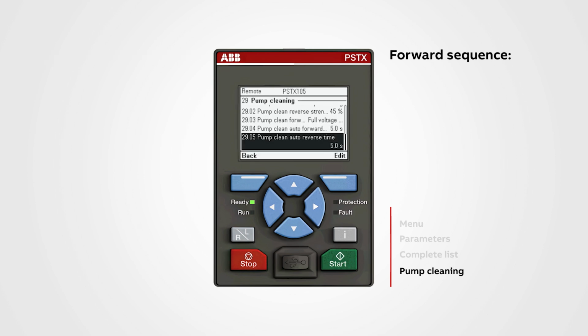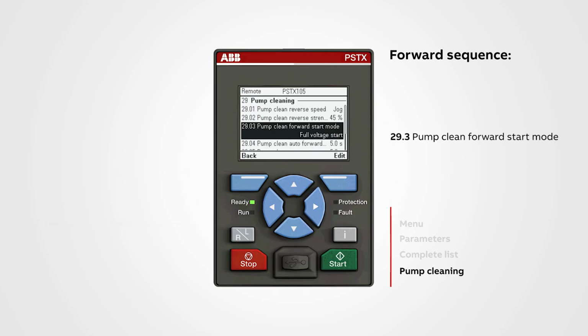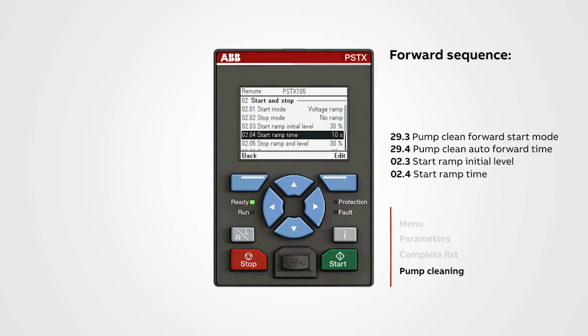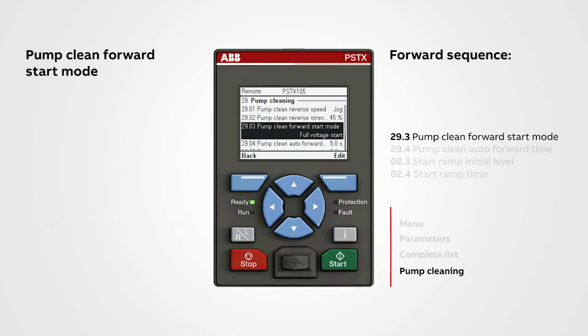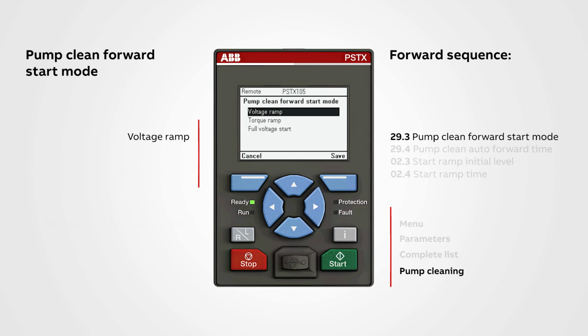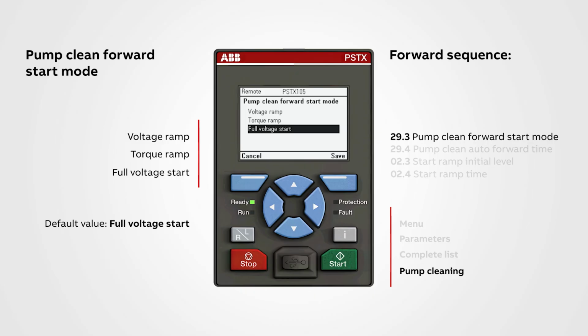So let us now move to the next step in the sequence, the forward direction, where we have 4 parameters to set: 29.3 and 29.4, related to ramp type as well as length of running the motor forward, and parameters 2.3 and 2.4, related to voltage and torque ramp. We start with the parameter 29.03, pump clean forward start mode. This sets the desired start mode. Voltage start ramp increases voltage linearly, torque start ramp increases torque in a predefined pattern, and full voltage start ramps up to full voltage within 1/3 of a second. The default forward mode is full voltage start, which is the most effective and fastest start possible for the soft starter.